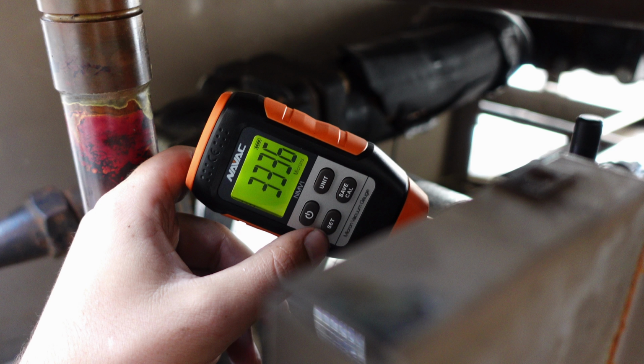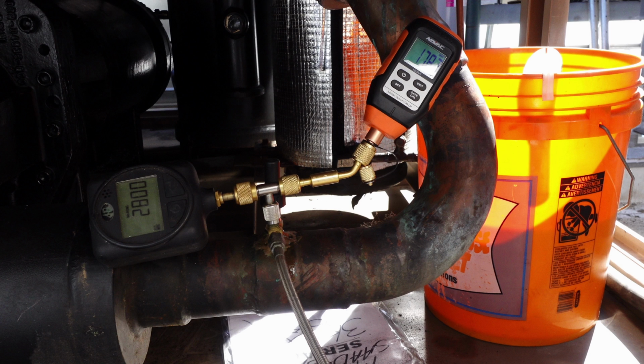To give some values to this, you want to get down to 500 microns, period. If you can get down to 400 to 500 microns, you're in a good range. And when doing these standing tests, ideally you're going to stay within 1 to 200 microns of your original starting point. Now if you've got an older system that you know is just going to have trouble...